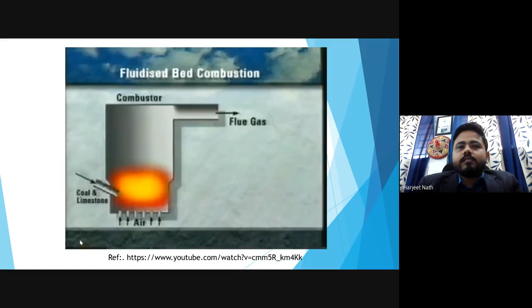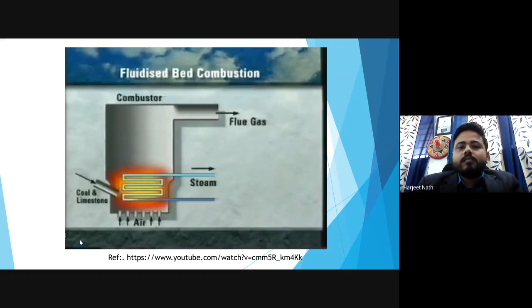Industry is that of fluidized bed combustion, FBC. FBC uses a technique which was first applied by the oil industry in the 1930s and has since been applied to solid fuel combustion. If a gas is passed through a bed of particles, the particles become suspended in the gas and are constantly mixed together in the upward gas stream. In this state, the mixture behaves much like a boiling liquid and is said to be fluidized. In a fluidized bed boiler, coal is burnt in a bed of ash and limestone. By immersing water pipes in the bed, the heat can be used to produce steam to drive a conventional steam turbine.